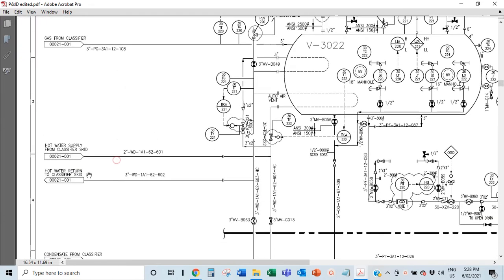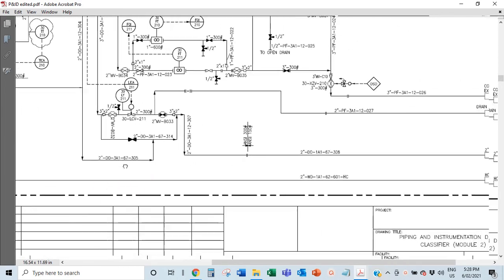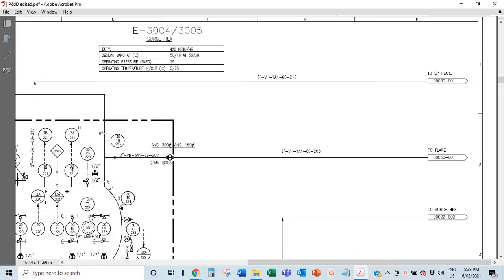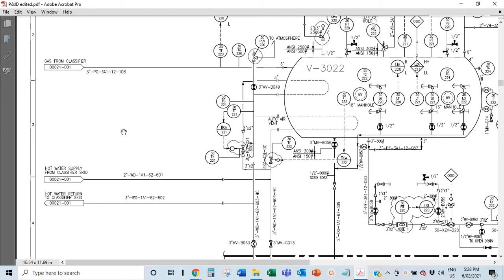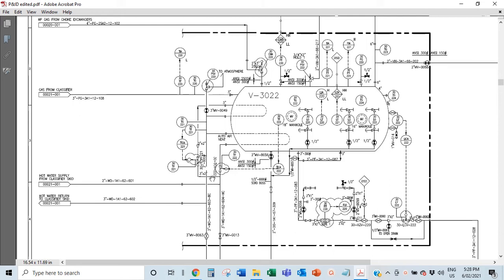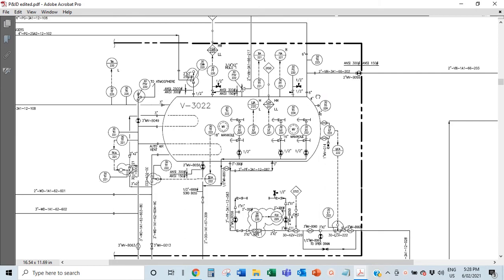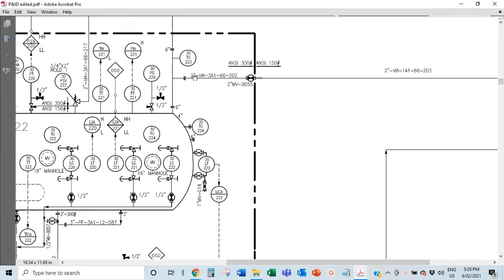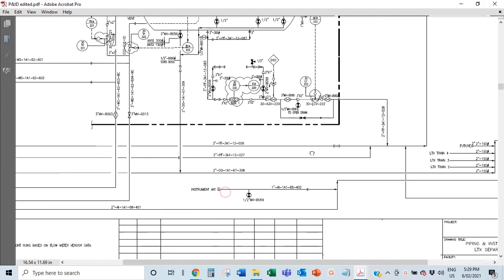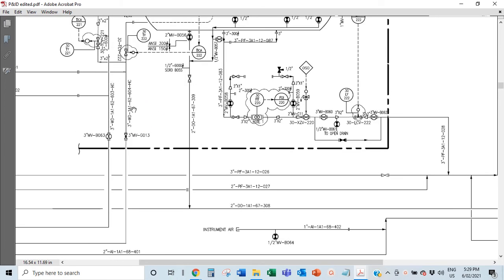Sometimes there may be errors in the P&ID, but that's why you do HAZOPs and reviews — to pick them up. Line numbers change when there is equipment in between, like a valve, heat exchanger, or pump. For example, '2 inch VH 3A1 66202' changes to '2 inch VH 1A1 66203' because of a valve in between — that's how and why line numbers change.